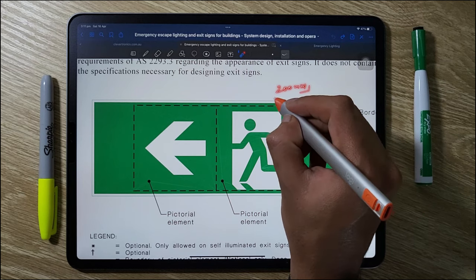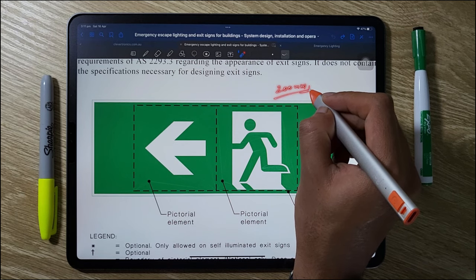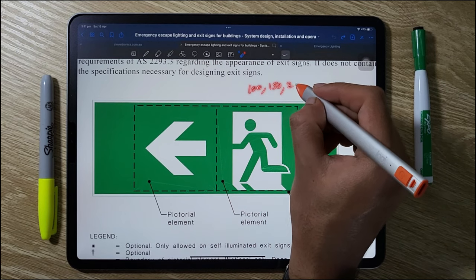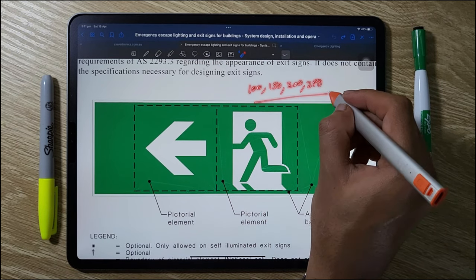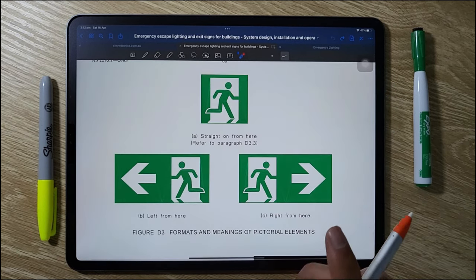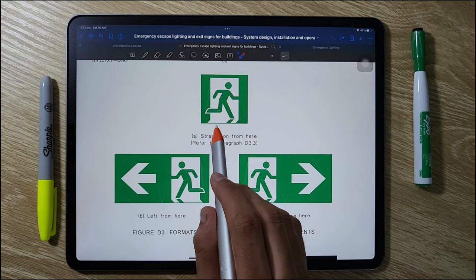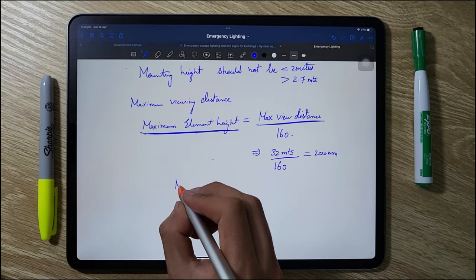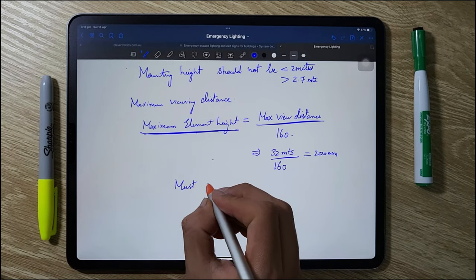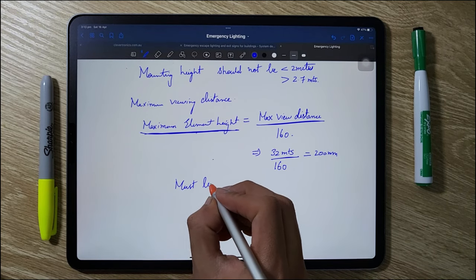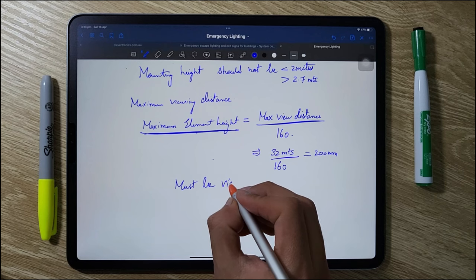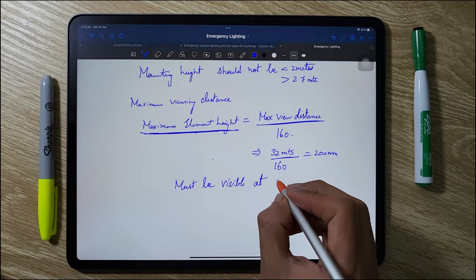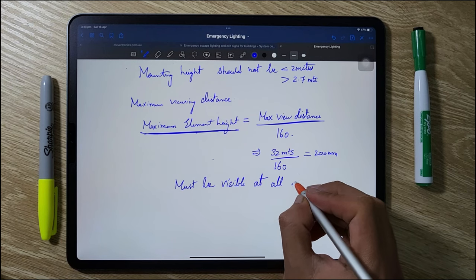The standard element height sizes are 100, 150, 200, and 250 mm. This is how the straight, left, and right directional emergency exit signs look. Emergency exit signs must be visible at all times, irrespective of whether mains power is operating or not. With this we have finished the designing of emergency exit signs.